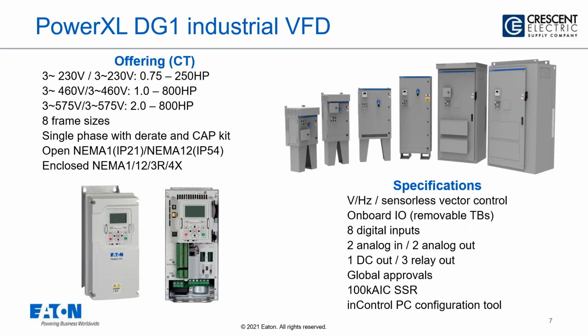And then if you need options to go out to maybe AC inputs or get RTDs or things like that, then there's option cards you can add to it as well. It does have a 100 kA short circuit rating paired with a specific group of breakers or fuses that's in our catalog. Anything we sell will be 100 kA if it's packaged. And once again, we have that programming environment which will allow you to utilize the InControl to go in and communicate with this product.